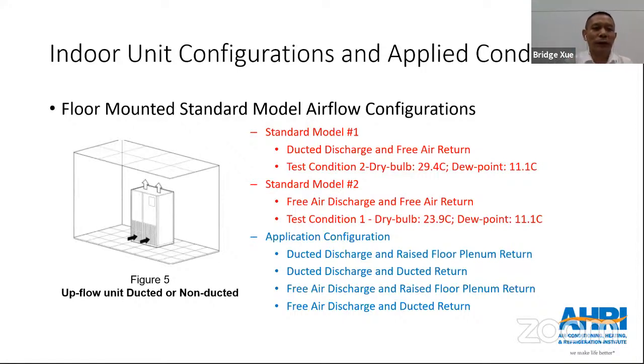So one more here is floor mounted standard model airflow configurations. They have two different standard models. The first one is ducted discharge and free air return, so condition two will be applied. The dry bulb will be 29.4 and the dew point is 11.1. And then standard model two will be free air discharge and a free air return, so condition one will be applied.